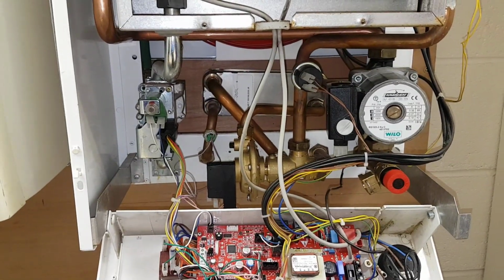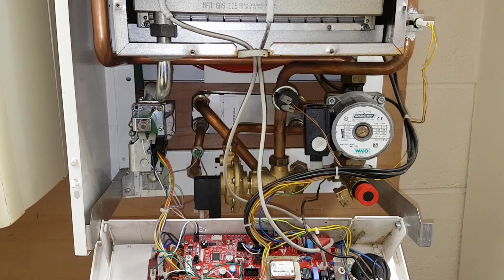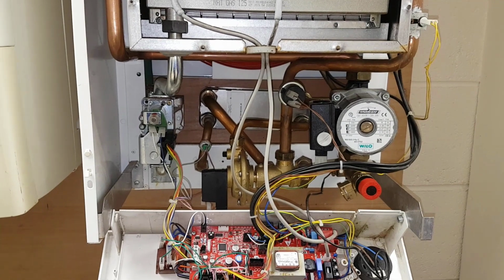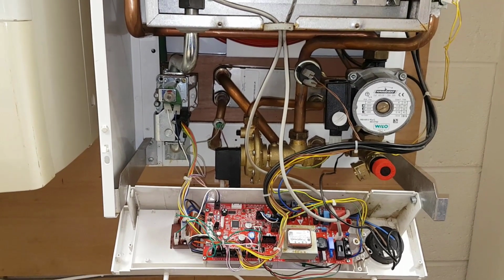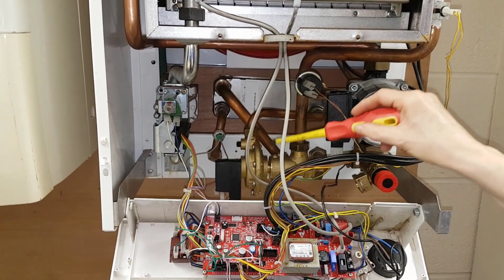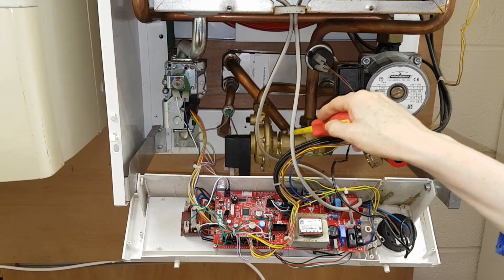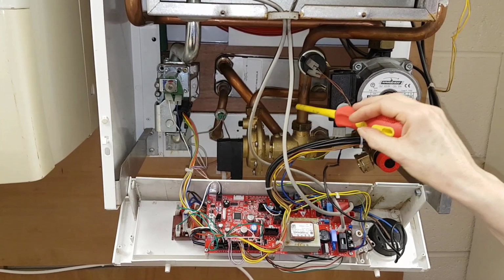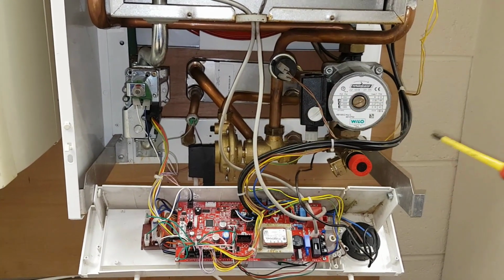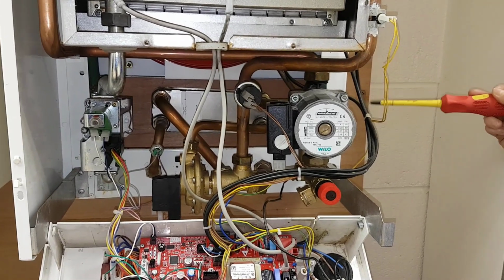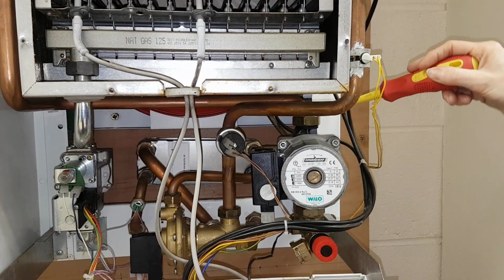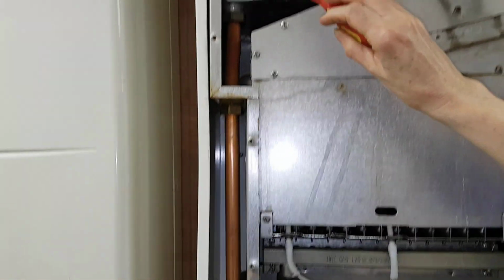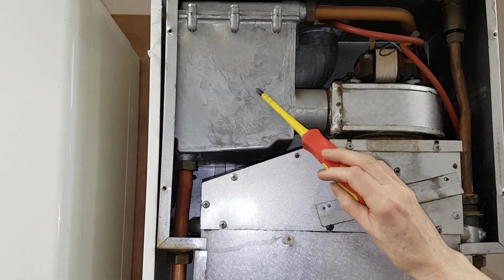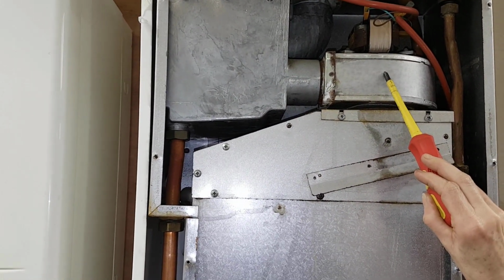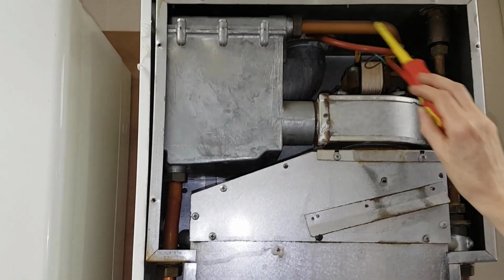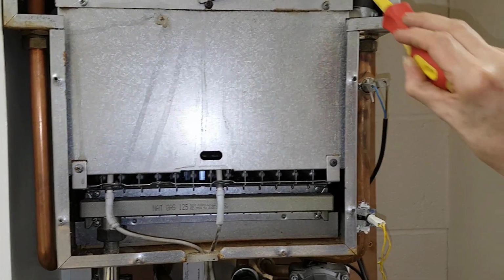Okay, so let's look at the central heating. The customer selects an external control, a room thermostat and usually a programmer, and that puts demand onto the boiler. That causes the diverter valve to be at rest for central heating on this boiler. In that position, it starts with the return coming out of the back of the pump, all the way up as before through the recuperator, which heats the water some more from the products of combustion from previous ignitions and burning. Then it comes round and down, all the way into the heat exchanger.